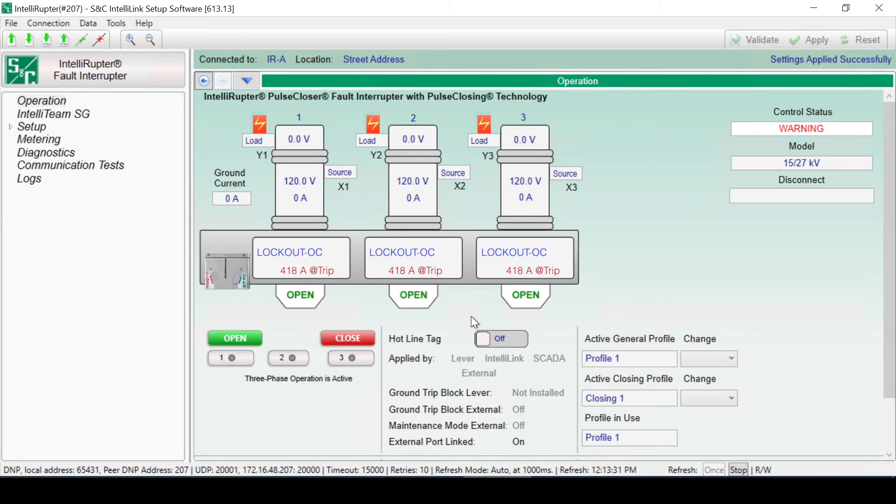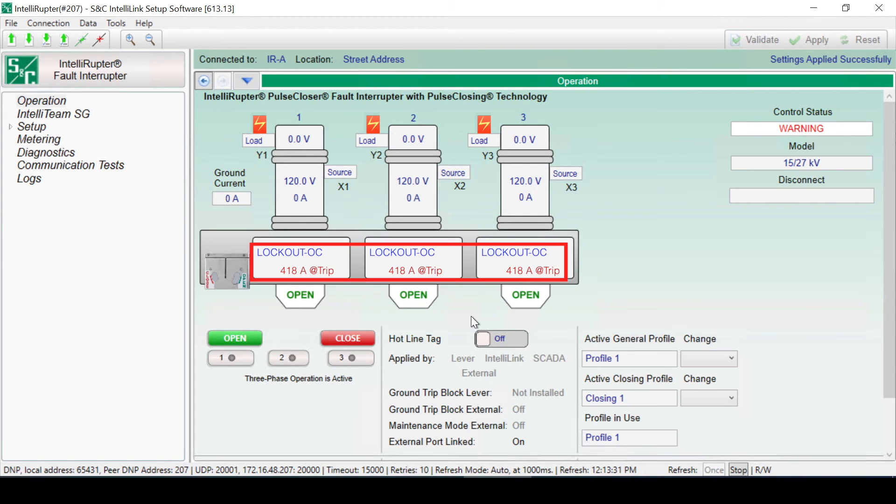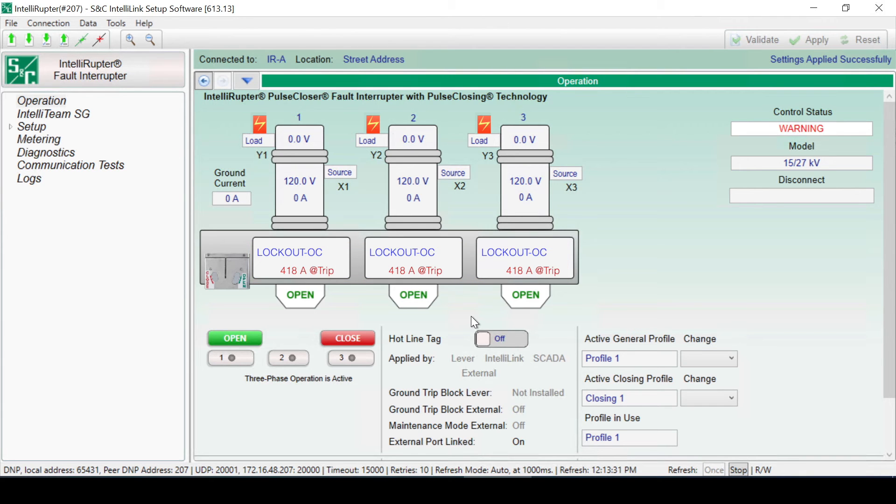If the fault interrupter has tripped and locked out, there will be an indication on the Operation screen. More information about the current that caused the lockout is available in the boxes below each pole. These indications can be cleared by either closing the open device or by clicking the Clear Latched Overcurrent button.